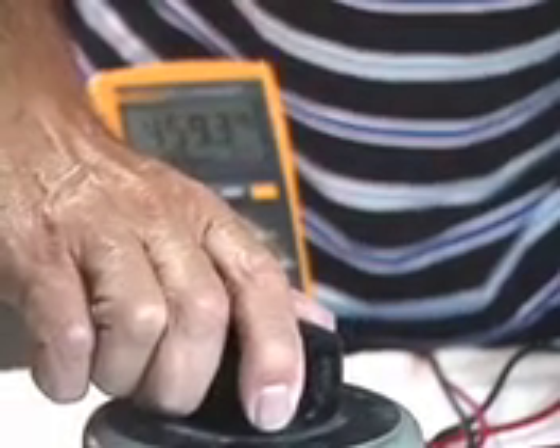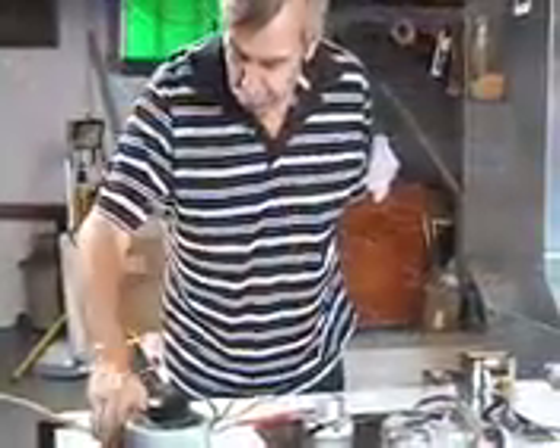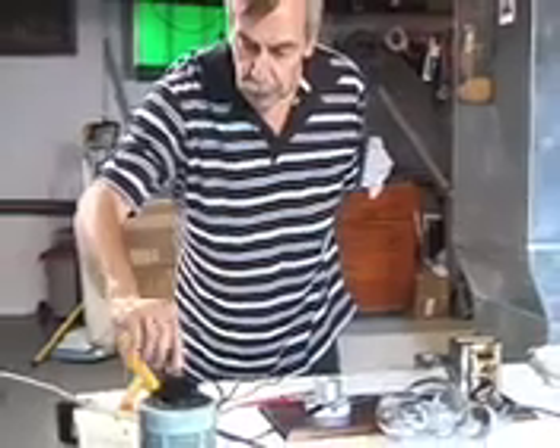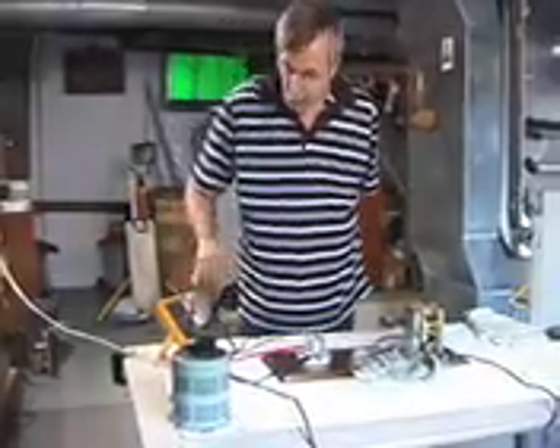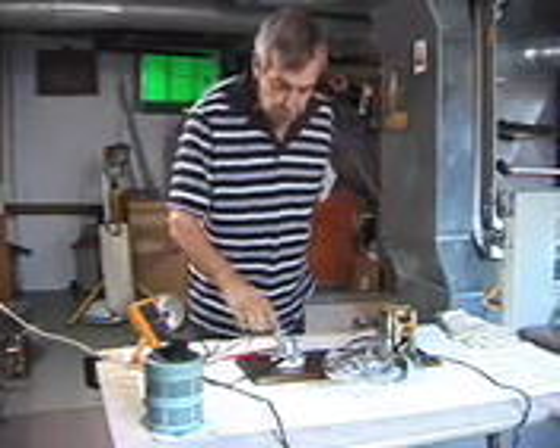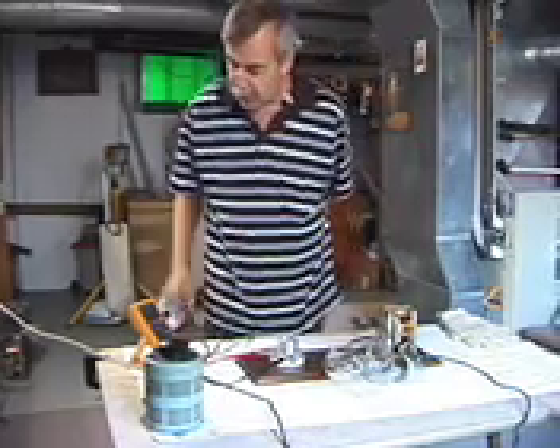I propose to plug the tube into this socket. I'll put my gloves on first so that I don't get the oil from my hands on the glass of the tube. The only way I know that the tube is getting enough voltage is by putting a voltmeter right across its filament terminals, like so, and then I will observe the voltmeter. In fact, we can do a dry run. I'm going to turn on the auto transformer, and I'm going to vary it from 0 on up to when we get the proper filament voltage across these two terminals. The proper filament voltage is 8.2 volts.